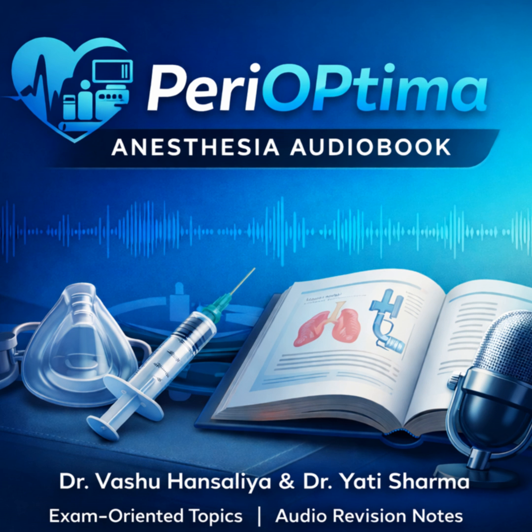Step 3. Vaporizers. Check that they are full. Check that the filler caps are tight, and then check the interlock system. Try to turn 2 vaporizers on at the same time. It should be physically impossible. Step 4. The big one. The low-pressure leak test. The gold standard here, and the one you must describe, is the negative pressure test, or universal leak test. You attach a special suction bulb to the common gas outlet.